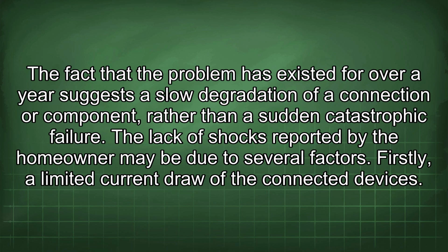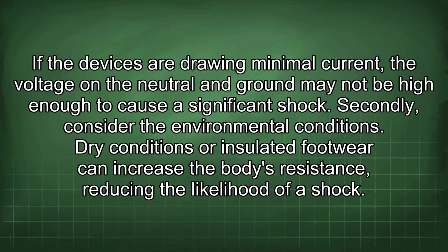The fact that the problem has existed for over a year suggests a slow degradation of a connection or component rather than a sudden catastrophic failure. The lack of shocks reported by the homeowner may be due to several factors. Firstly, a limited current draw of the connected devices. If the devices are drawing minimal current, the voltage on the neutral and ground may not be high enough to cause a significant shock. Secondly, consider the environmental conditions. Dry conditions or insulated footwear can increase the body's resistance, reducing the likelihood of a shock.